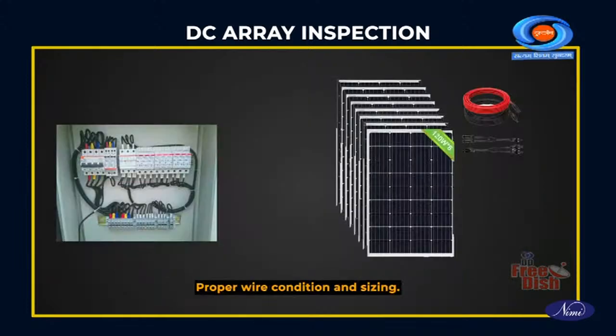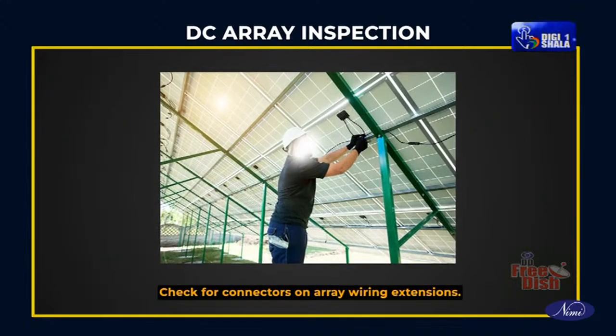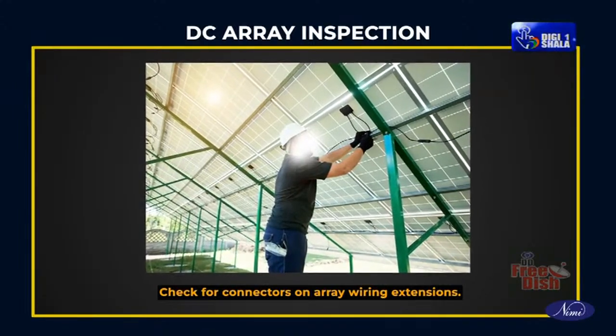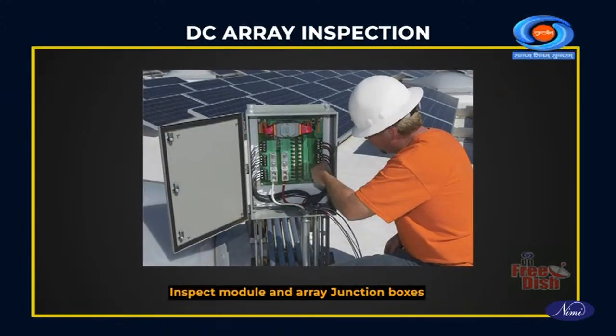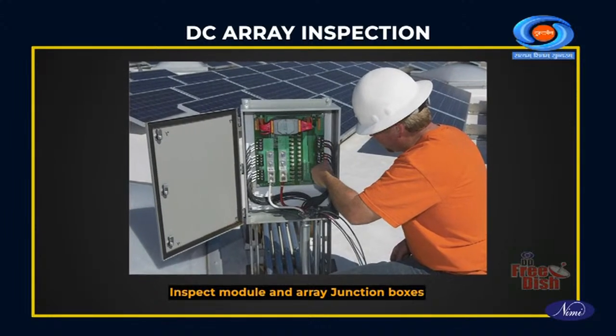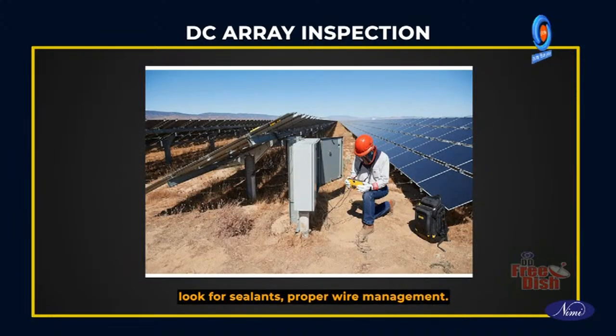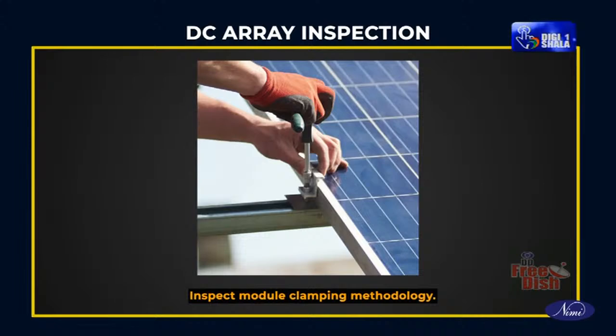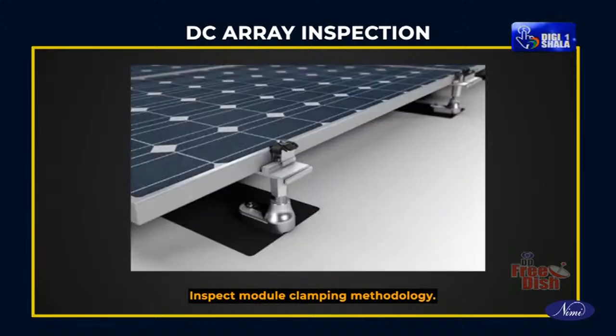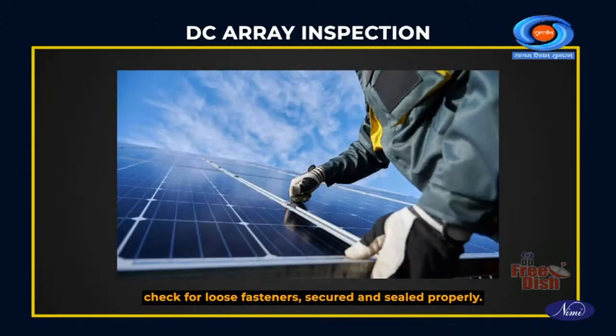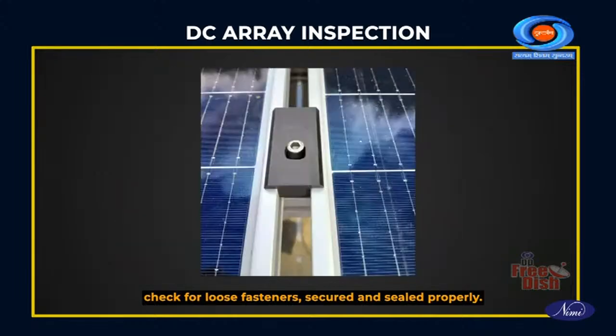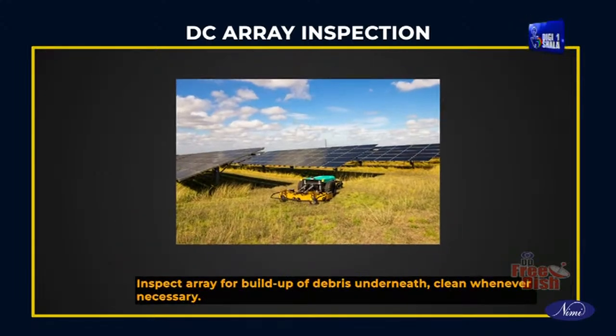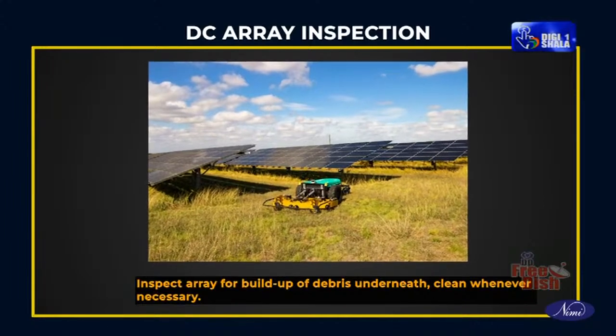Proper wire condition and sizing. Check for connectors on array wiring extensions. Inspect module and array junction boxes. Look for sealants, proper wire management. Inspect module clamping methodology. Check for loose fasteners, secured and sealed properly. Inspect array for buildup of debris underneath.